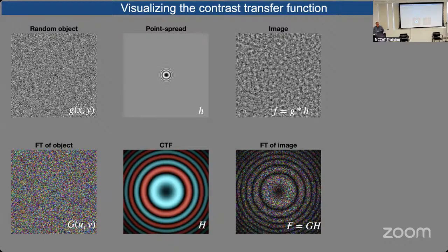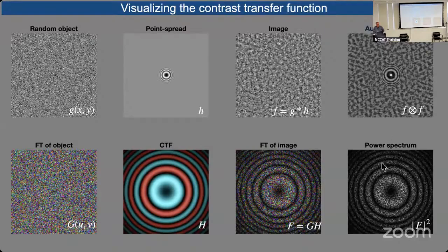Now, when you're sitting at the microscope, you actually get a display that looks like this. This is the magnitude squared of the Fourier transform. That's the power spectrum. And the power spectrum is the thing that I showed you before. It shows you what is the magnitude of the various Fourier components that the image contains. And so again, you see these Thon rings. So that's the Fourier transform. No one displays that. They display this, which is just the same, just colors are removed, basically.